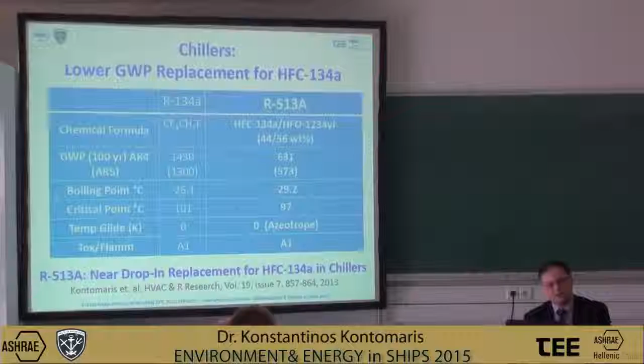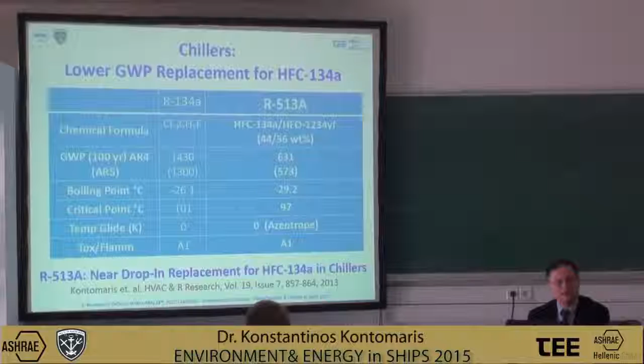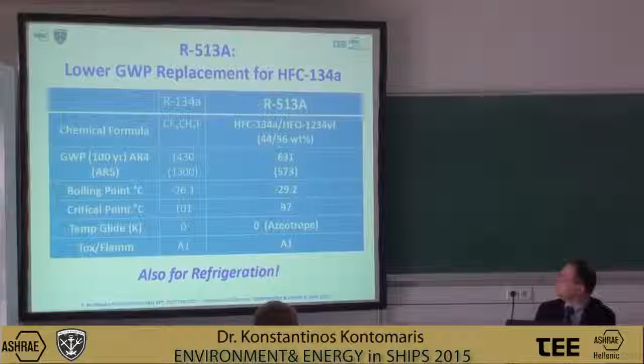The theme in these fluids that I mentioned so far is they all achieve near drop-in replacement of the incumbent fluid, and they are all non-flammable, and they all move in the right direction of reducing GWP significantly. Although in the future we may seek to reduce the GWP even further, but for now it makes sense to take the step that is feasible today. More details you can find in the literature. And of course, this fluid can also be a replacement for 134A in refrigeration applications, although it was developed primarily for chillers, but 134A has also been used for many refrigeration applications, so 513A could be a replacement for those applications as well.